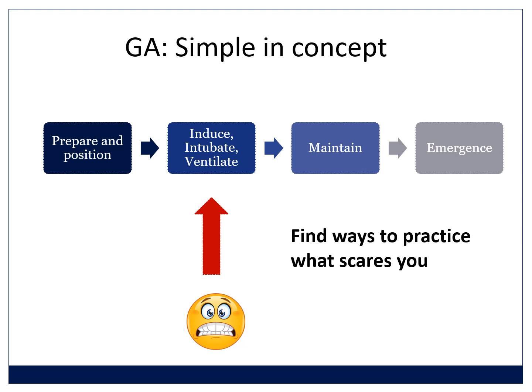Make sure you've done this before your first general anesthetic on a machine, and play with the different ventilatory modes to make sure that you can ventilate a false lung. It's really easy to practice, and really, because it's so easy, it's not really an excuse that the first time we're learning how to use a ventilator is on a patient.